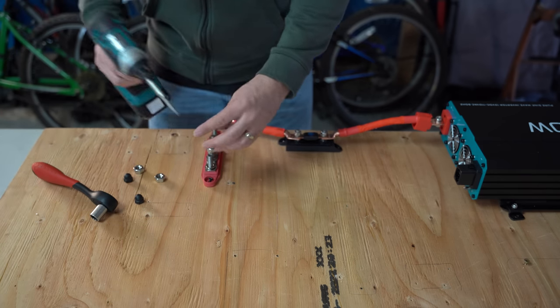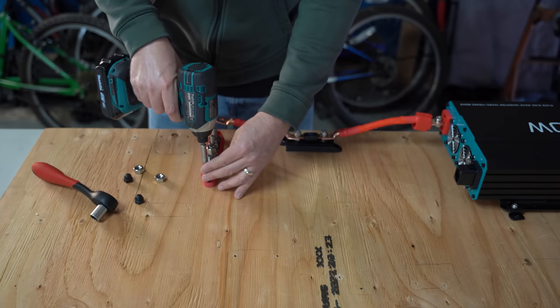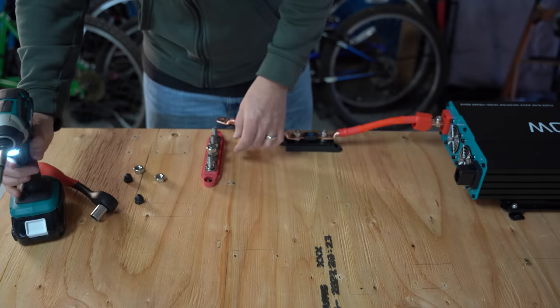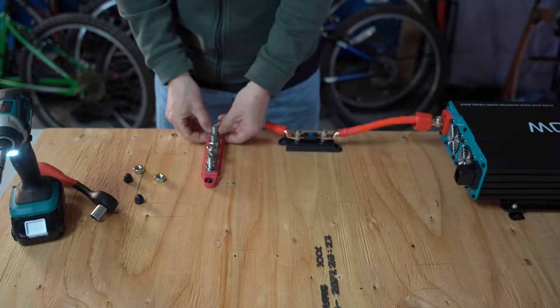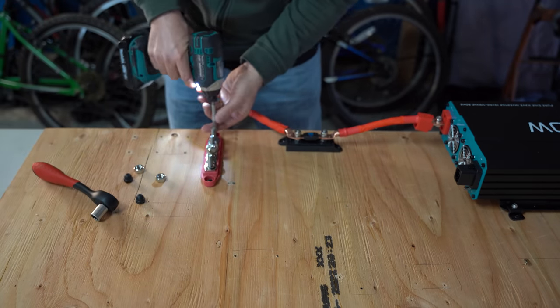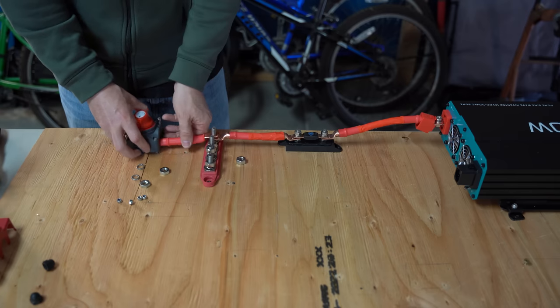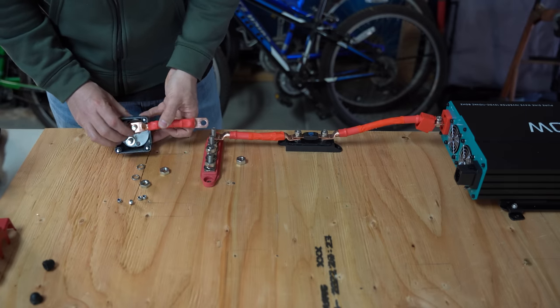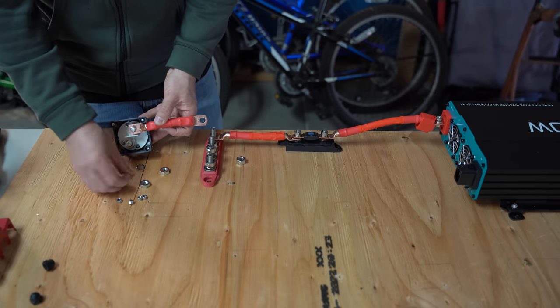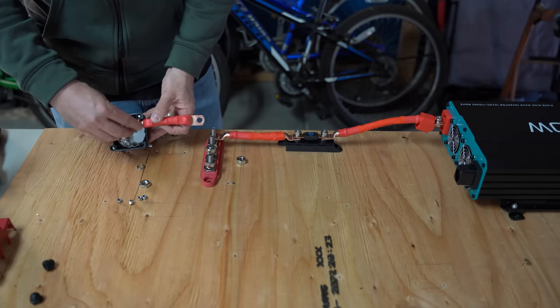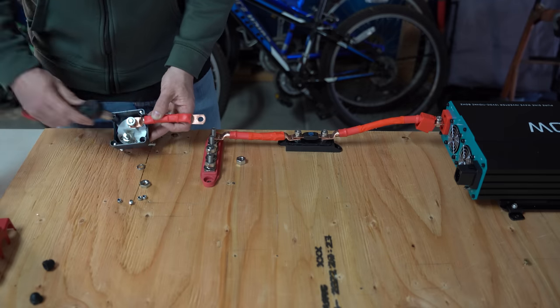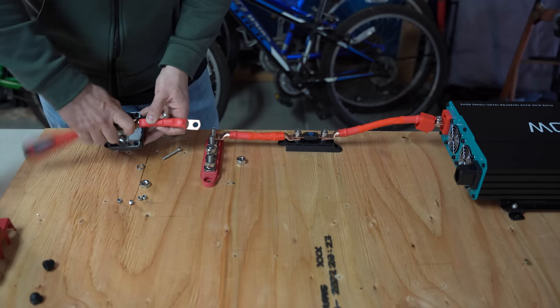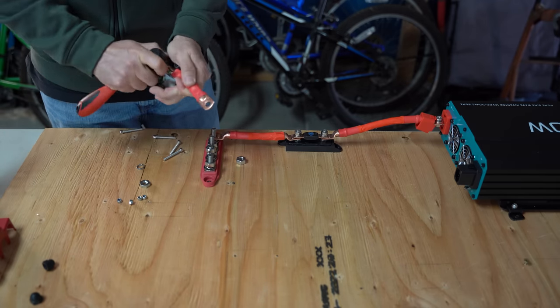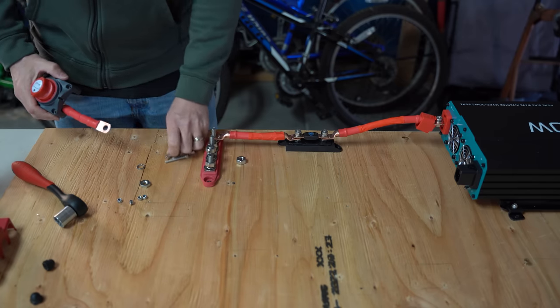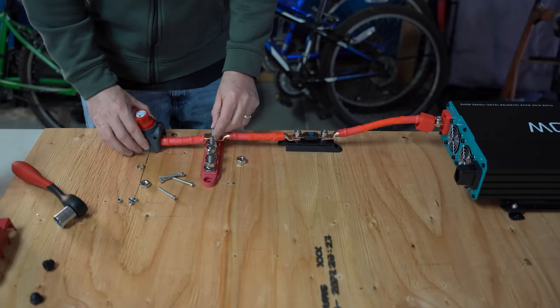Think of this as a hub where we'll connect different devices that send or receive current. From the bus bar, I'll repeat the process of sizing and customizing our cable, then connect it to the switch. Our system will have two switches, but for this particular one, I need the ability to send a lot of amperage through it. This particular switch is rated for 275 amps, which is more than enough for the 200 amp maximum current that we're going to pull from the battery.